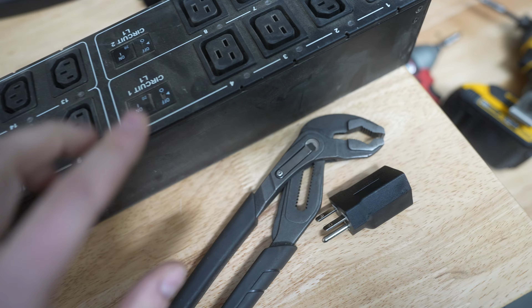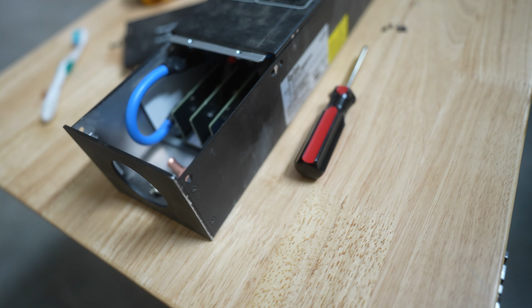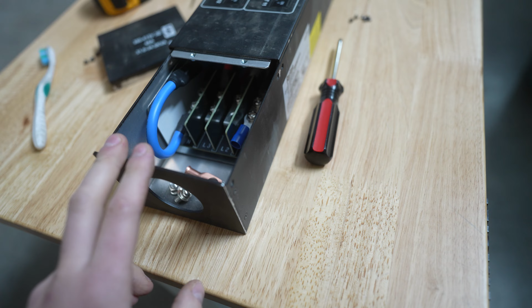Our power is going to be coming out of this hole here, that's 6 gauge. It's going to be running along our racks and then all the way to our panel. Our panel is 400 amp, 415, 3-phase. Again, each leg is 240. It's running 2 parallel runs of 4-aught cables all the way to the transformer. And you can watch us run those wires. Go to our channel, and you can see how we're connecting those to the transformer and how we're connecting the panels. You can see the finished product, or us finishing it up there.